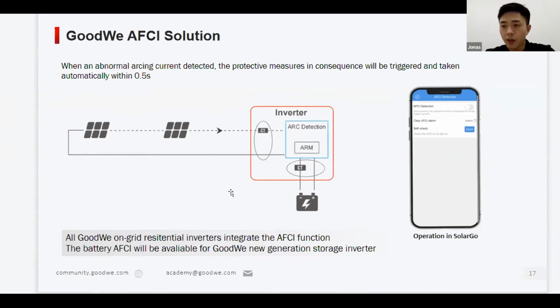So if we write the identification software in our inverter, we call it the AFCI module, then it can identify the arc fault with the arc detection ARM chip. When there is an arc fault, it can determine whenever there is an occurrence of abnormal arcing current, and the protective measures are triggered and taken automatically. It's like to say, if we detect the arc fault, it will cut off the AC relay of the inverter, both on the PV module side and the battery side.